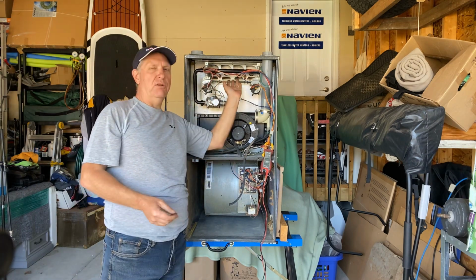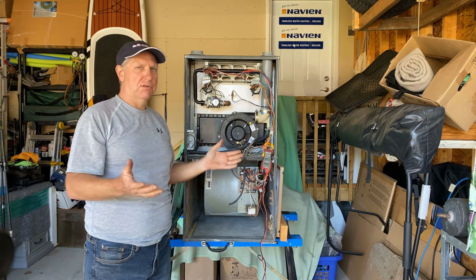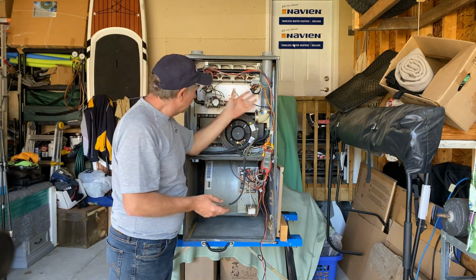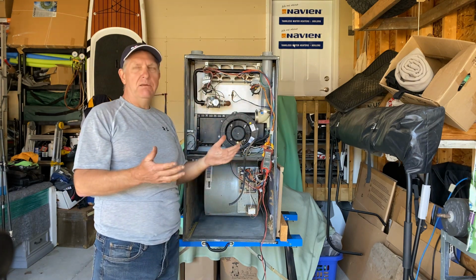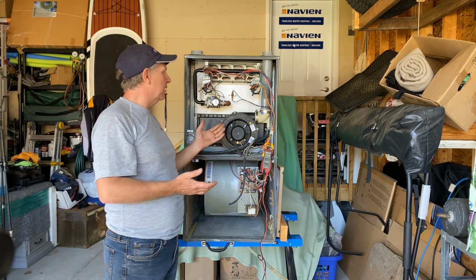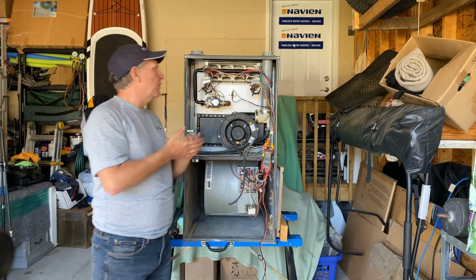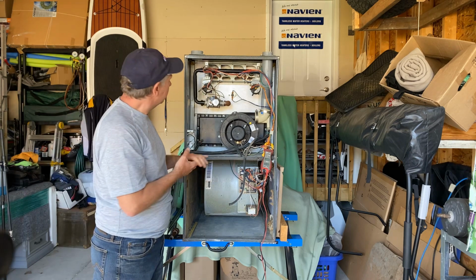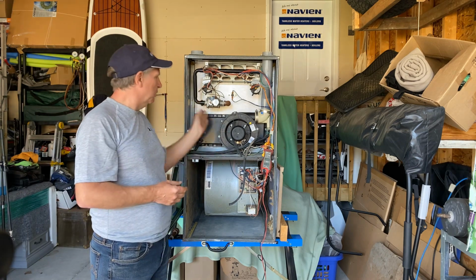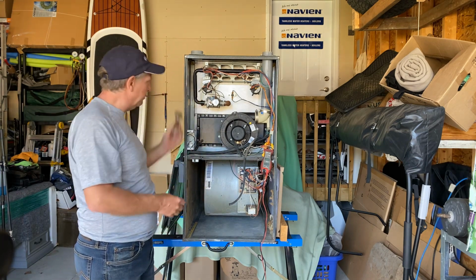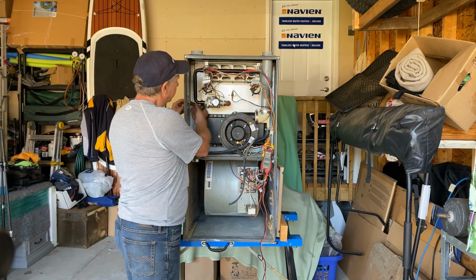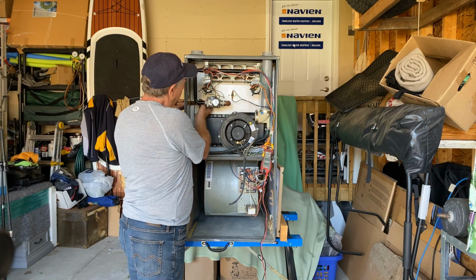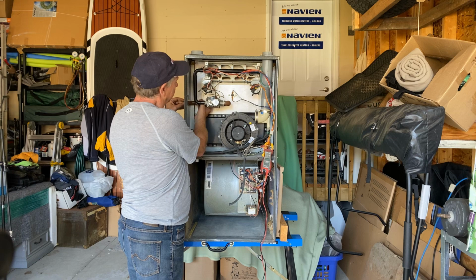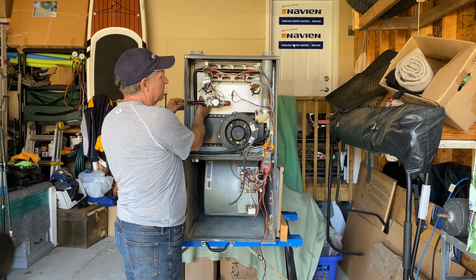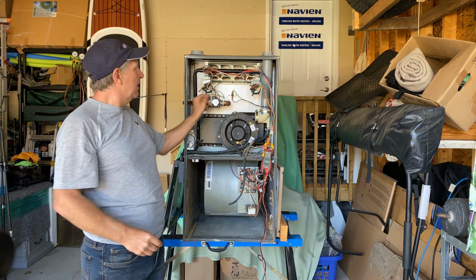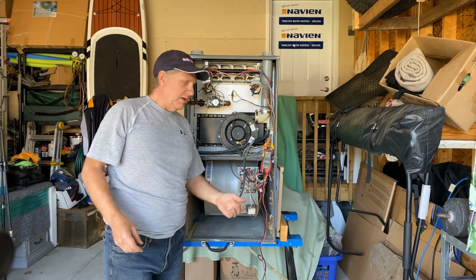Some things you're going to look for is dirty burners. Look into the heat exchanger. Do I see any sooting, any plugging, anything like that? So again, this looks pretty clean, not such a big deal. So that's the burner in and out. Then I'm going to reconnect my piping, get that done. Get my pipe wrenches out, tighten that union up nice and tight so it doesn't leak. And we're set to go there.